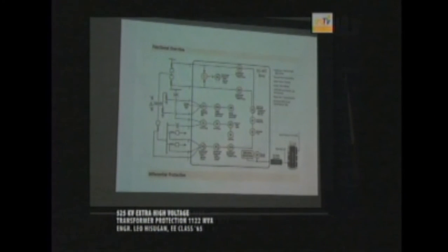This is the single line meter relay diagram of the transformer here, and we're using an SEL 487E relay. The E here is being utilized for volts per hertz protection. This is an improvement of the SEL 387E relay. So far, any questions?